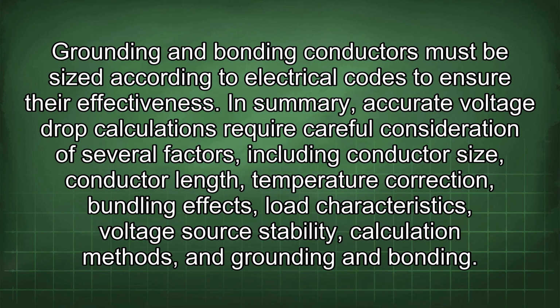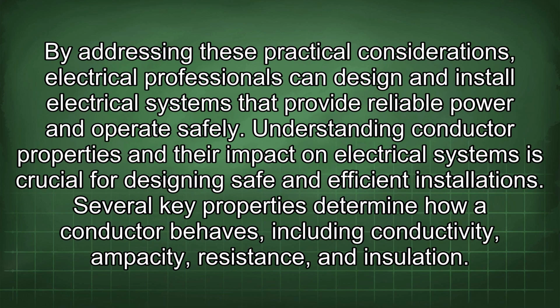In summary, accurate voltage drop calculations require careful consideration of several factors, including conductor size, conductor length, temperature correction, bundling effects, load characteristics, voltage source stability, calculation methods, and grounding and bonding. By addressing these practical considerations, electrical professionals can design and install electrical systems that provide reliable power and operate safely.